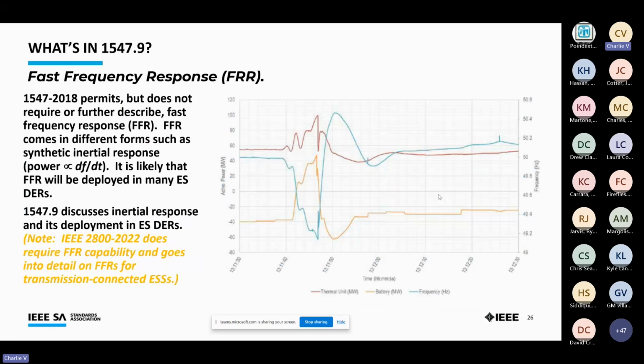I just want to touch on this. Fast frequency response capability is required in IEEE 2800, the new inverter-based resource interconnection standard for transmission-connected resources. 1547.9 discusses it as a desirable capability, but depending on what the upstream people responsible for frequency regulation and management flow down, 1547.9 has a good discussion of what FFR is and how it relates to the performance capabilities of a 1547-compliant energy storage system. The good news is, if implemented consistent with the approach in IEEE 2800, there would be no conflicts with an energy storage system performing fast frequency response - it'd still be within 1547.9 performance standards in general.